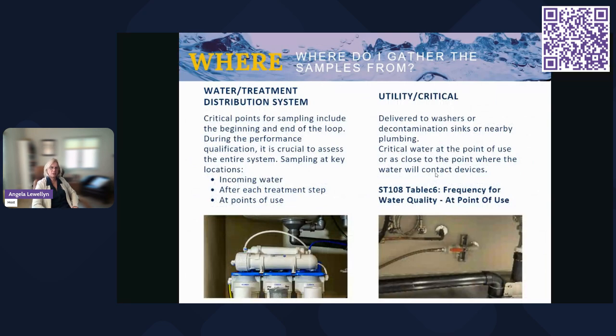There's a water distribution system, which we talked about a little bit earlier. If you have a filtration system and incoming water, you test it as the water comes in before it's treated, then again after the treatment step, and again at the point of use. Remember we talked about how to identify if I have critical water in my sink. There's a faucet that comes straight from the filtration system or feed water tank that you can test right here at your third bay sink, so you're testing at the point of use as well.